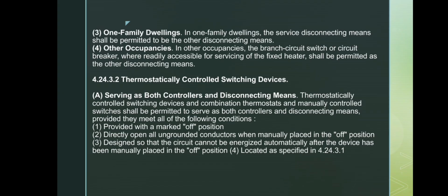Next, we continue with the rules of disconnecting means in different occupancies. One-family dwellings: in a one-family dwelling, the service disconnect is allowed to serve as the other disconnecting means for the fixed heaters. Other occupancies: in other types of buildings, the branch circuit breaker or switch may be used as the other disconnect as long as it is readily accessible for servicing the heater.